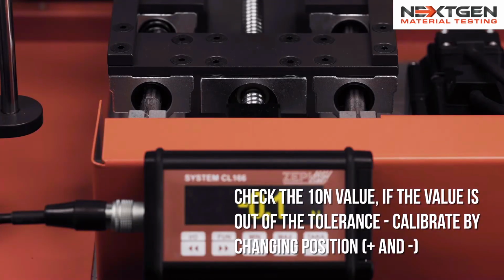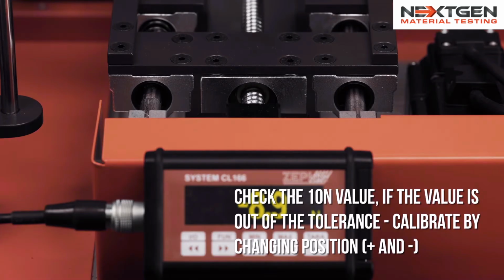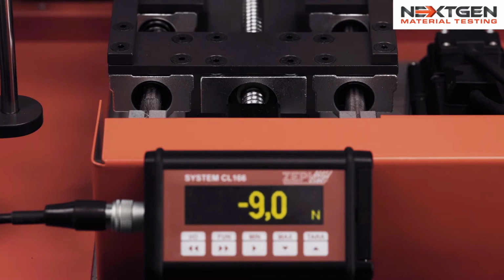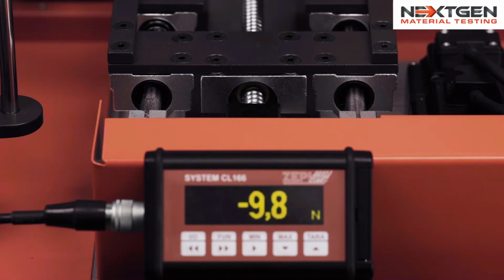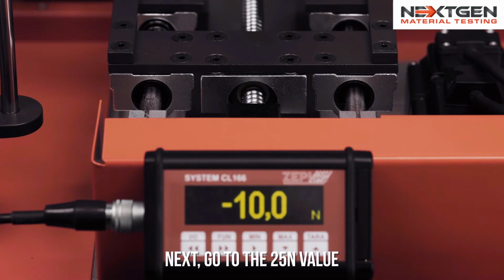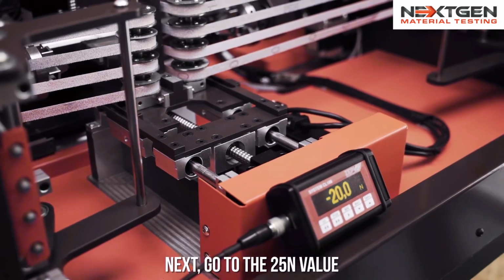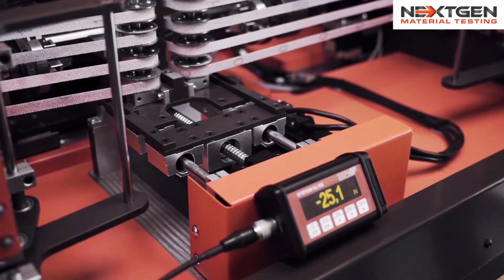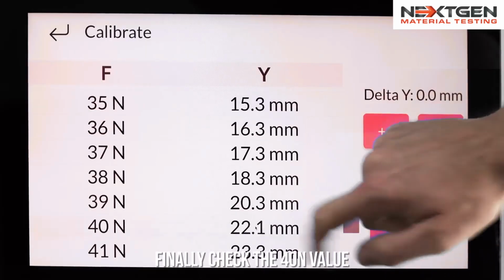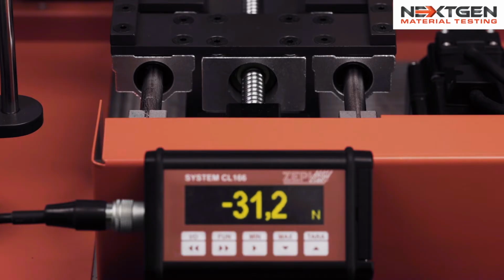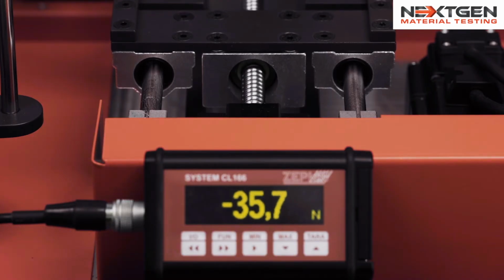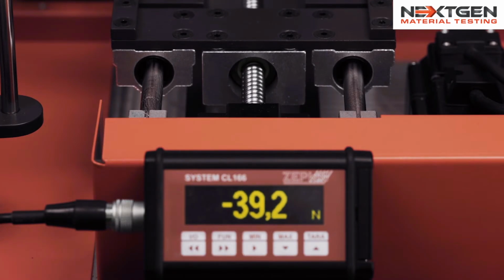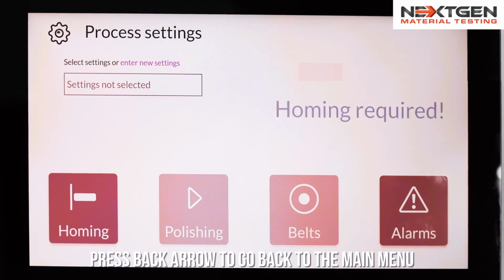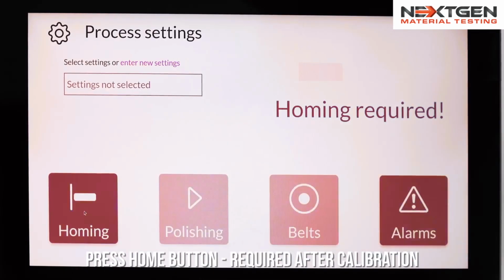Check 10N. Adjust if out of tolerance. Proceed to 25N. Then check 40N. Return to main menu. Press Home after calibration. Remove the measurement unit.